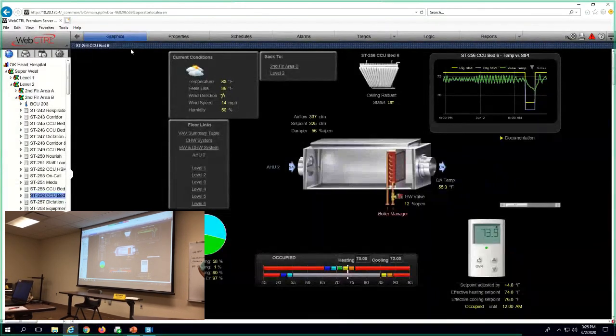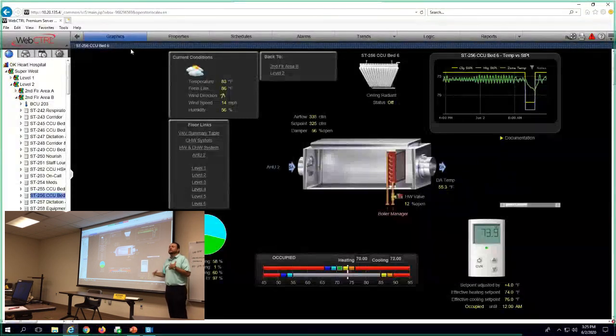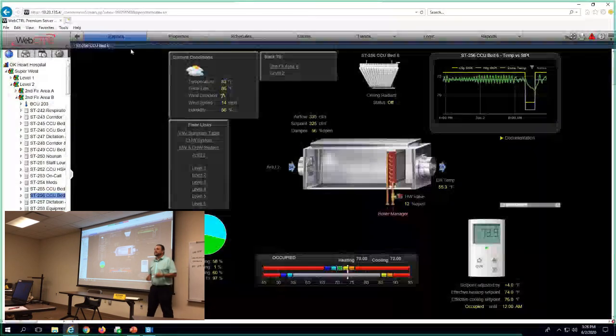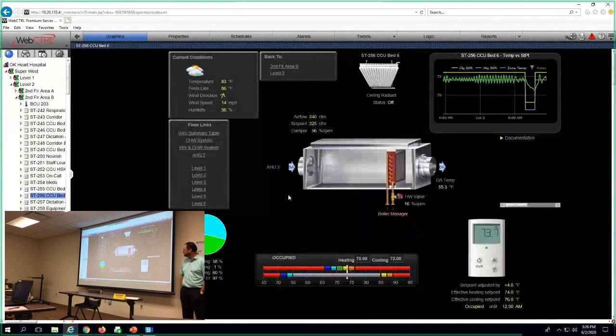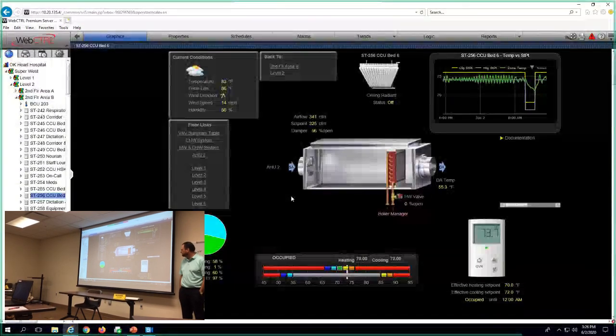I want to make sure we're communicating the right thing. How did you get to 70 as the set point? Let's use this one as an example. Is it the effective heating set point that gives us the baseline, or is it 71? It's wherever the last user on the front end left it. You have to hit accept to see it change. If you go down to 0 instead of +4 and hit accept, your effective heating and effective cooling change on the right-hand side. In my mind, the neutral set point, the baseline, would be 70 degrees.